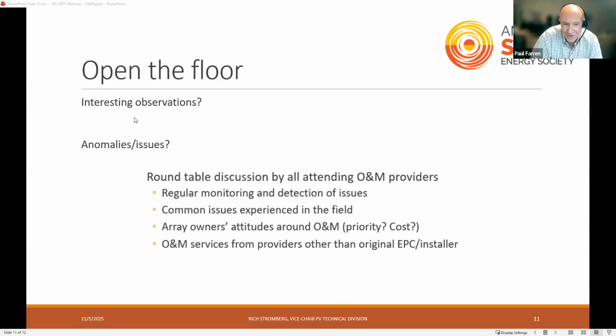There's an argument back and forth where if you use DC optimizers, you're using much higher voltage, less wire, smaller wire. The fact is that optimizers used to fail a lot. Now they've evolved to the point where, like, I have a system with 64 optimizers. It's been out for 3 years, and 2 of them have failed in 3 years. But they're very easy to replace. You just take them out and put them back in. A truck roll's a truck roll. It's $500 to do anything. Right.